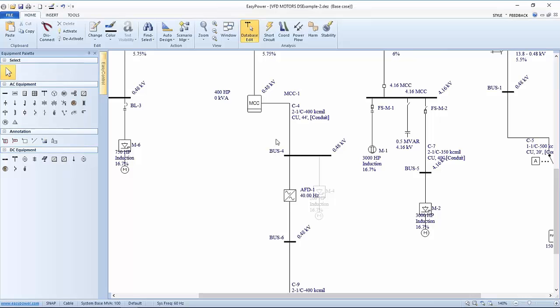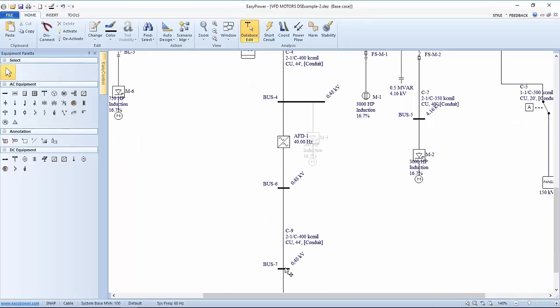There's a small amount of difference in the arc flash calculations, and as I say, I'll have to get back to you on why I'm not seeing an arc flash energy downstream of my controller, given my AFD fault time protection.